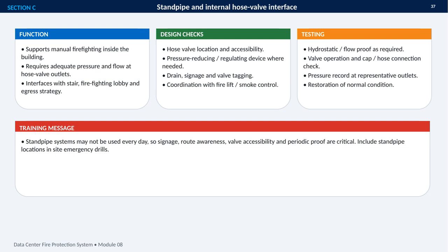I need to confirm that hose valves are easy to find and access, and that pressure-reducing or regulating devices are provided where conditions require them. Drainage, clear signage, and accurate valve tagging also matter. The standpipe arrangement must be coordinated with the fire lift and smoke control systems, so these elements work together during an emergency. Testing should demonstrate that the system performs as intended.